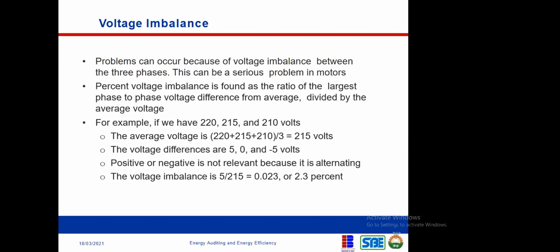Positive or negative is not relevant because it is alternating. You remember we were talking about alternating current here and all of that. So the voltage imbalance here is the highest difference, which is 5 in our case, divided by the average voltage, which is 215. When you do that division, you have 0.023, and when you multiply by 100, you have 2.3%.